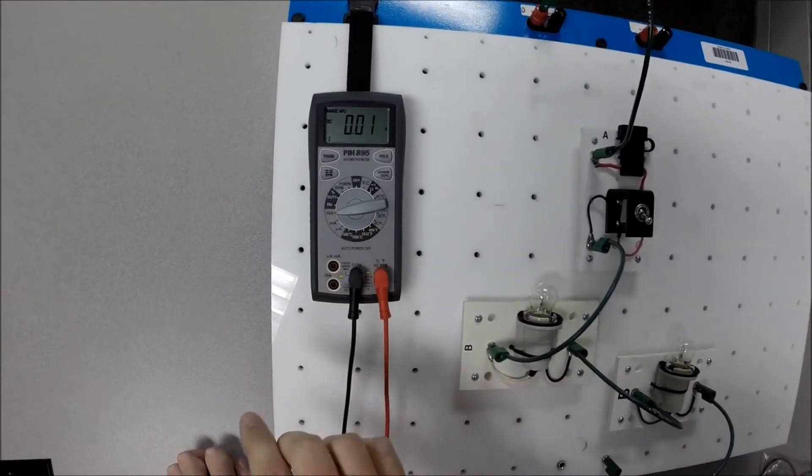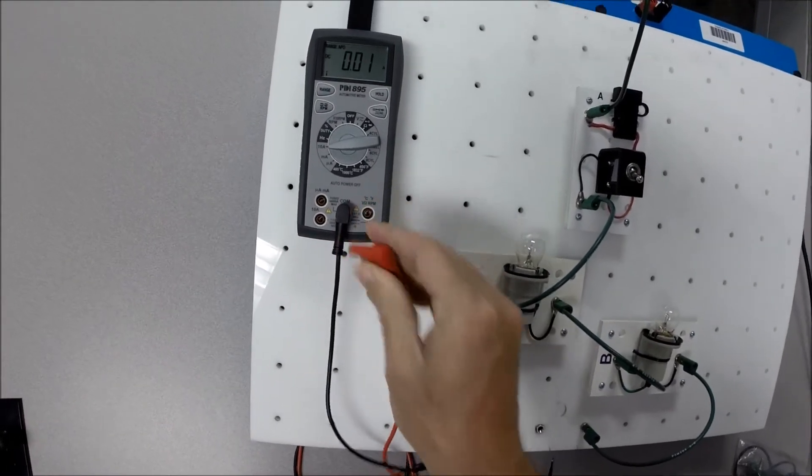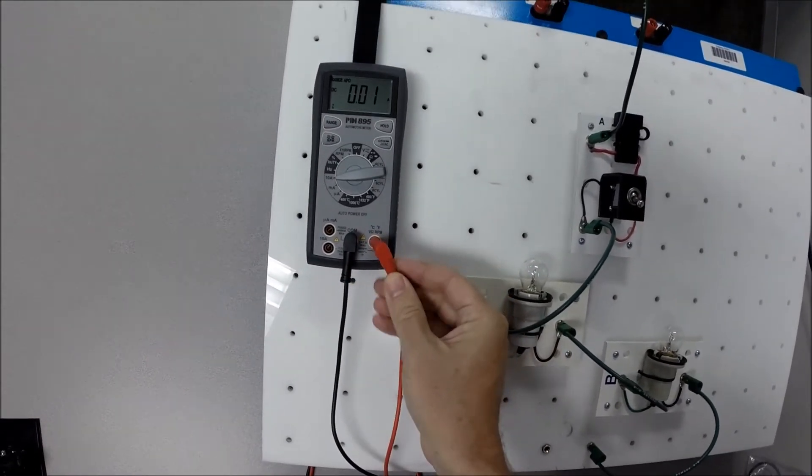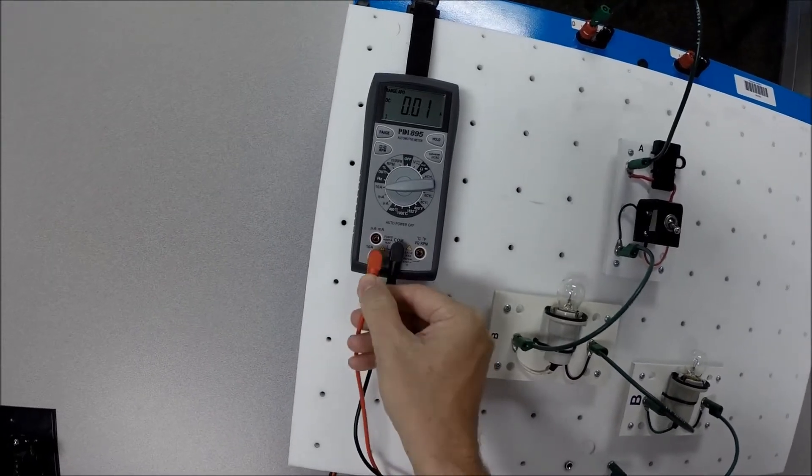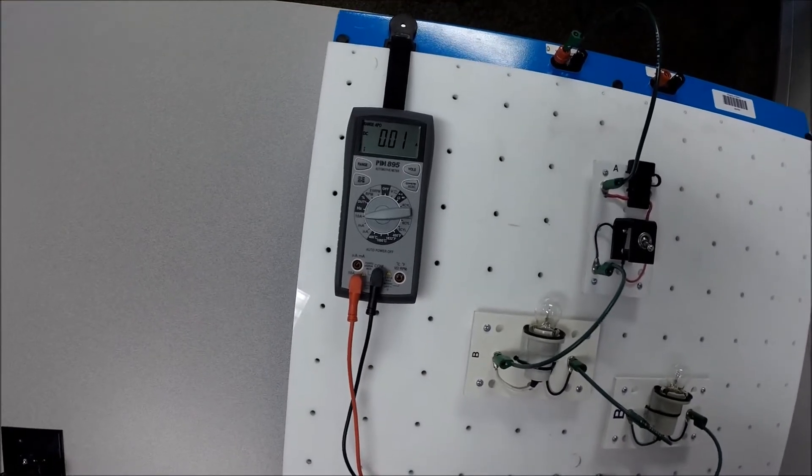Start on the 10 amp scale, because we don't want to blow a fuse. Now, very important that we remember to move our leads. So, we're going to take our red lead from the voltage slot, and we're going to move it over here to the 10 amp slot. So, now the meter is ready to measure amperage.